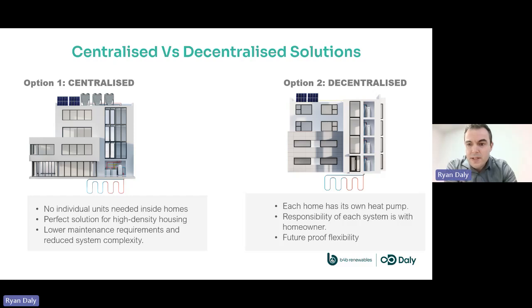So moving on to the different options with heat pumps in terms of heat networks, we've got centralized or decentralized solutions. Centralized is where you have your main plant in the plant room, and then you've got heat distribution pipework feeding all the flats or apartments. And you can see in this example, we've got boreholes shown here and also a fan collection unit on the roof. So both of them can be combined as a heat source.